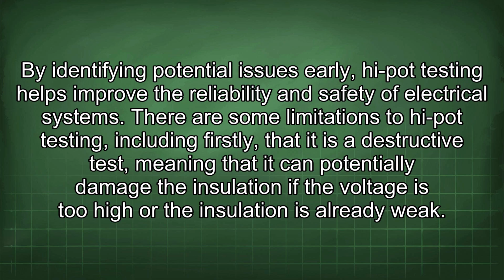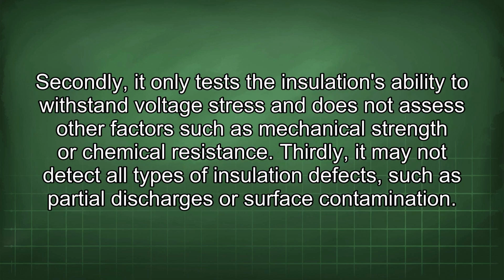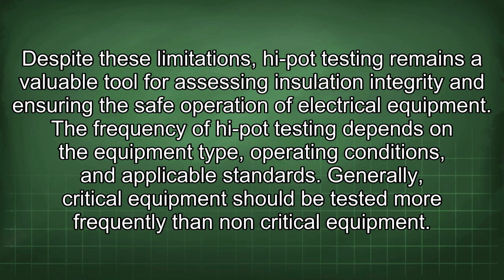There are some limitations to hi-pot testing, including firstly that it is a destructive test, meaning that it can potentially damage the insulation if the voltage is too high or the insulation is already weak. Secondly, it only tests the insulation's ability to withstand voltage stress and does not assess other factors such as mechanical strength or chemical resistance. Thirdly, it may not detect all types of insulation defects such as partial discharges or surface contamination. Despite these limitations, hi-pot testing remains a valuable tool for assessing insulation integrity and ensuring the safe operation of electrical equipment.